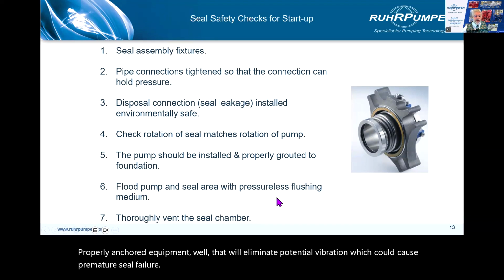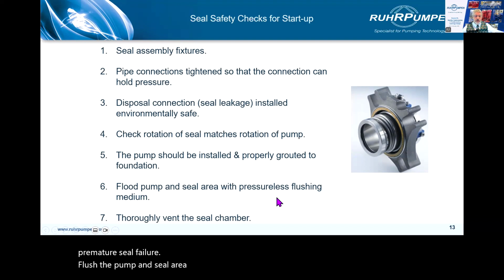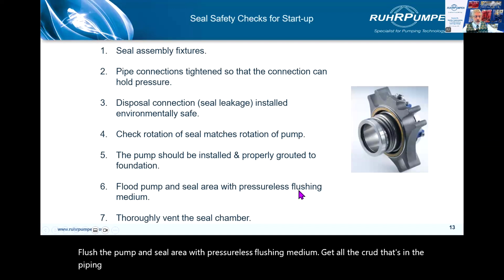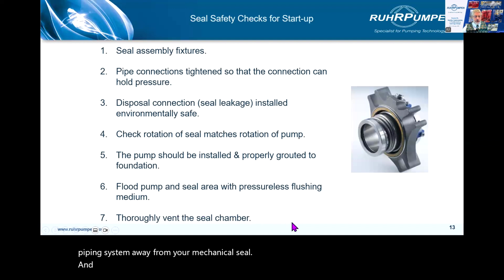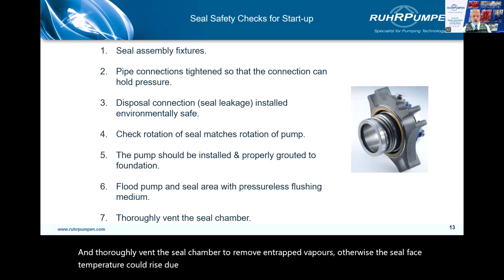Flush the pump and seal area with pressureless flushing medium. Get all the crud that's in the piping system away from your mechanical seal. And thoroughly vent the seal chamber to remove entrapped vapors. Otherwise, the seal face temperature could rise due to insufficient lubrication, which could damage the seal.